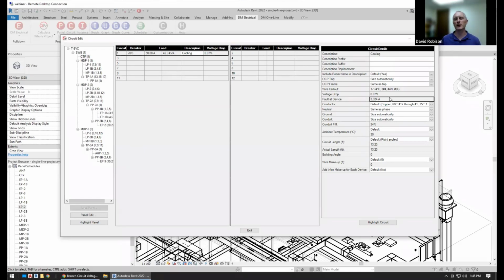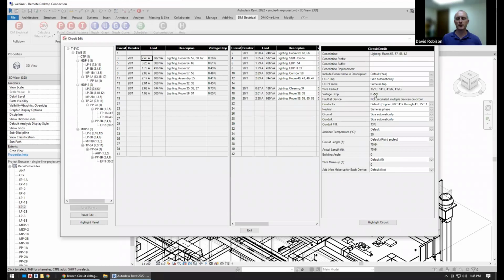For a piece of equipment, you might want to know what the fault is for making sure that the disconnect is rated properly. For something like a bunch of receptacles in an office, you're not worried about the fault at your receptacles, and it would have to be a different fault at each place anyway. So for those circuits that have multiple devices, we just say, hey, we're not calculating it. There's too many devices. If you did need the fault at those devices, you would need to model it differently. You could model it as electrical equipment essentially and get the fault there.